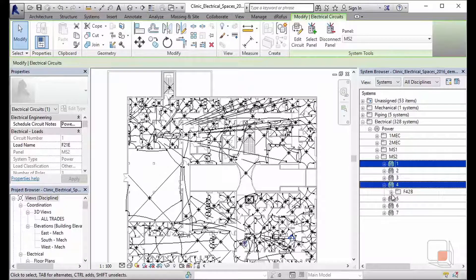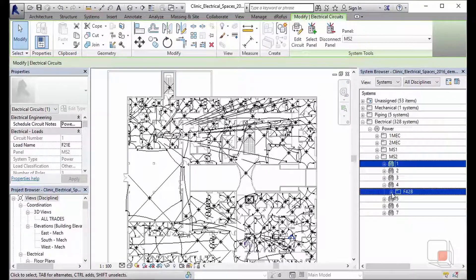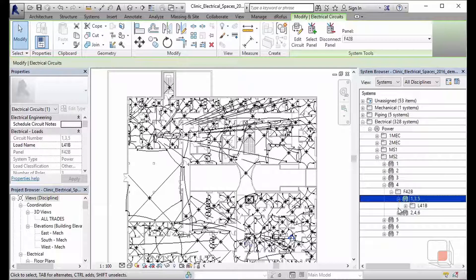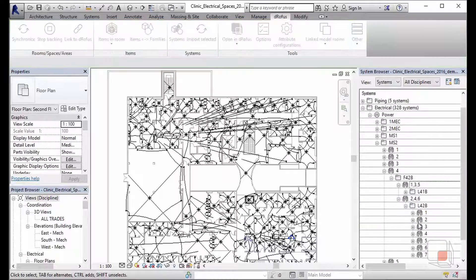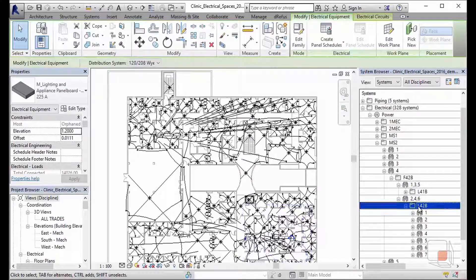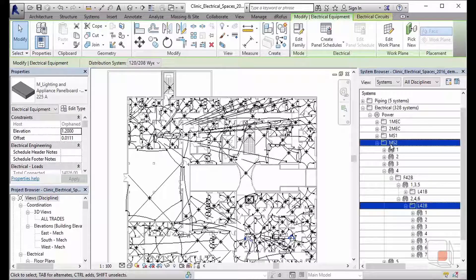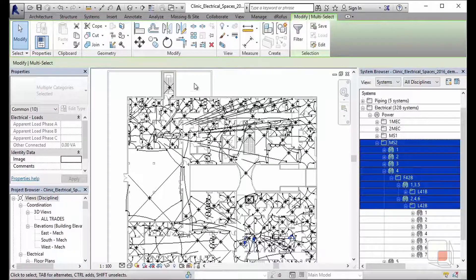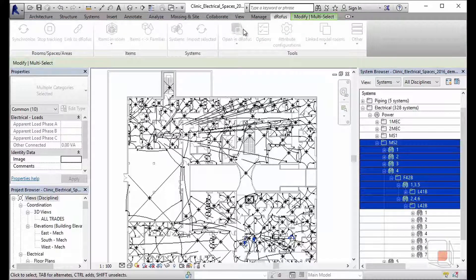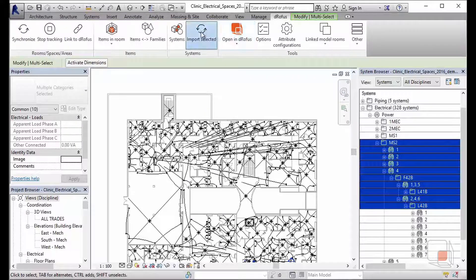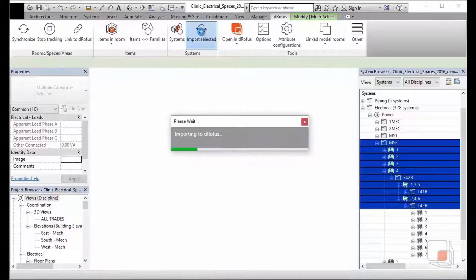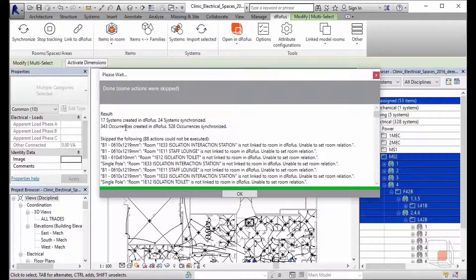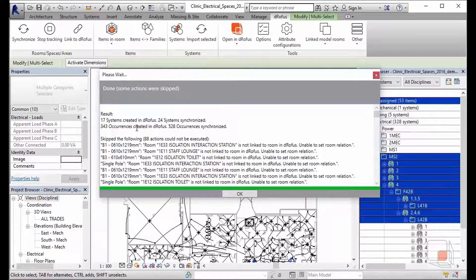What I can also do is drill even further into my Revit systems, all the way down to the actual components that might be powered. These could be light fixtures, switches, and so forth. I want to just import a portion of my Revit model. So I've done a shift selection from the actual panel all the way up to the item itself, the light fixtures. In this case, when I do import selected, I've imported 17 components in my system and 343 occurrences that have been imported from my Revit environment.